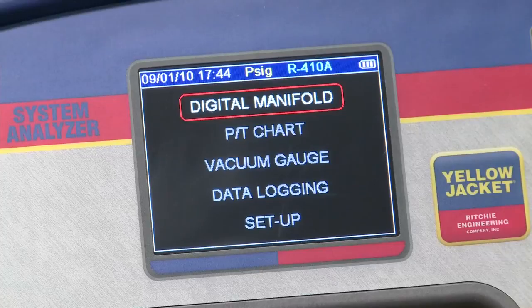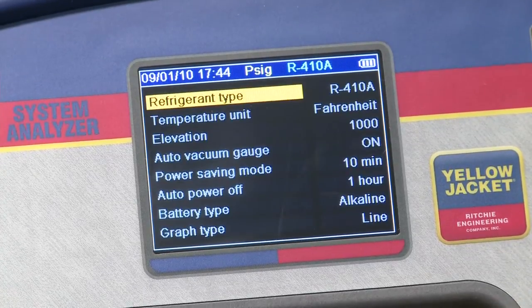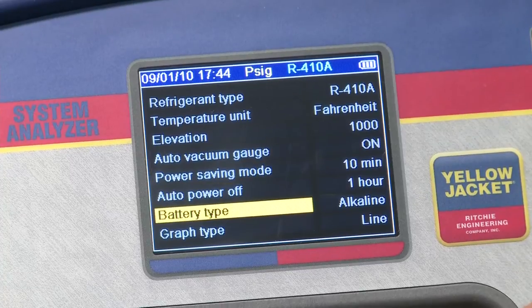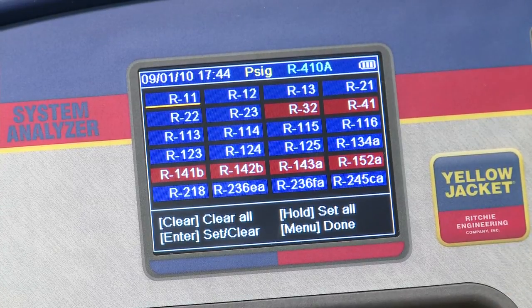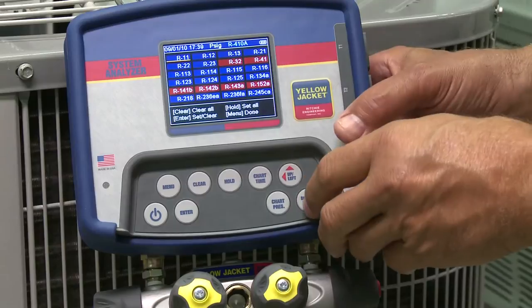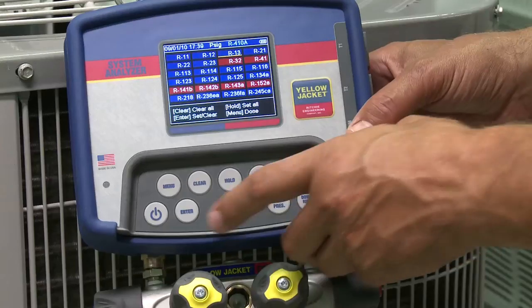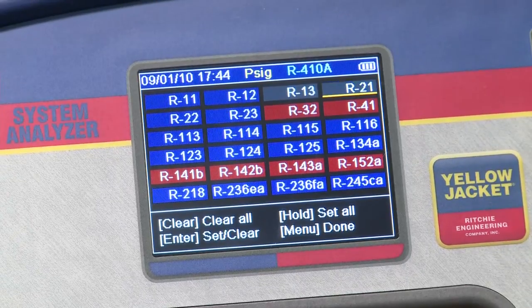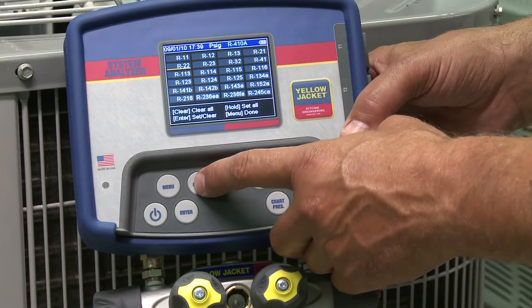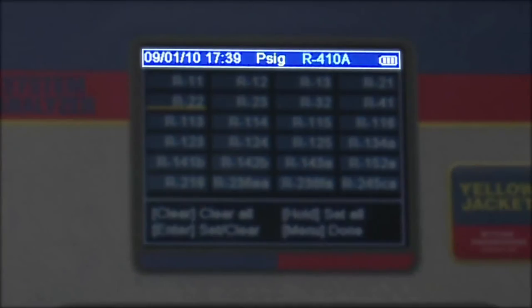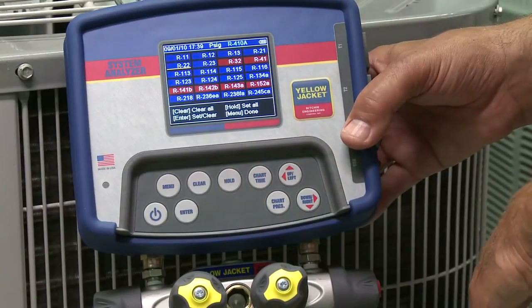When you get to refrigerant, you have the option of setting up a favorites list to reduce your list to the refrigerants you use the most. Set the list by going to the setup menu and scrolling to refrigerant favorites. All of the refrigerants are currently set as favorites, indicated in blue, or red if they're flammable. Move the yellow cursor with the arrow keys to the refrigerants you don't want as favorites and press enter. They'll turn gray and will no longer appear on your quick search screen. If you want to reactivate them as favorites, press enter again. The clear key will clear all favorites except the active refrigerant shown at the top of the manifold screen, and the hold key will set all refrigerants as favorites.